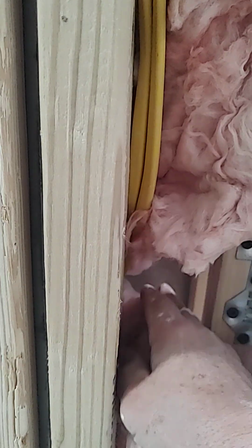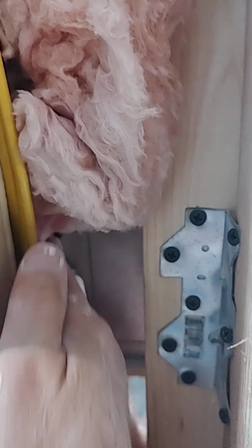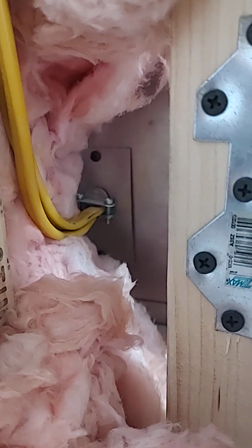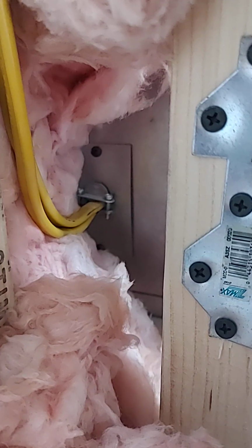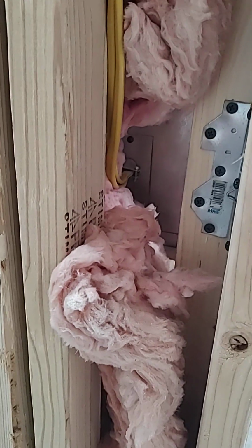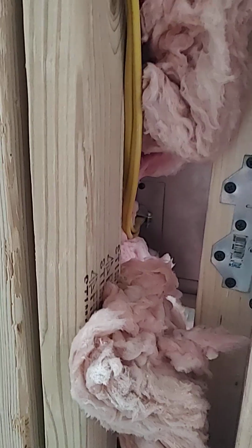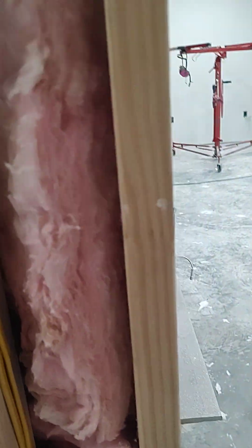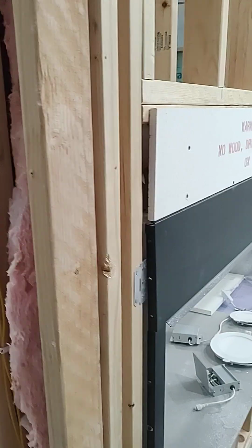One of the things that is really kind of bothering me is this is a ventless fireplace, and I'm going to pull this insulation back, and you can see that there's a junction box there, and that gets framed in. And you cannot frame a junction box in. So before we proceed any further, I get hold of the manufacturer and find out. I'm not aware of any NEC code that allows that to happen, and you cannot access that through the top of the fireplace. So kind of a bridge to cross.